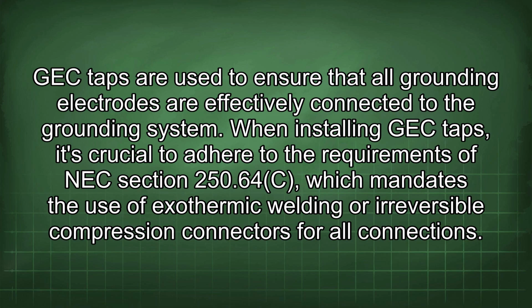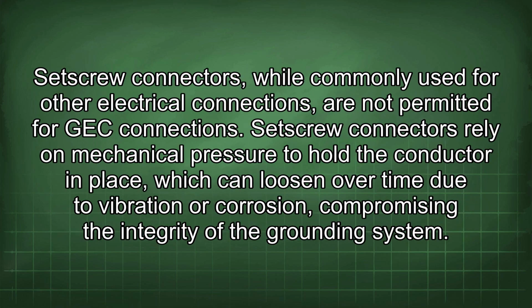When installing GEC taps, it's crucial to adhere to the requirements of NEC Section 250.64(C), which mandates the use of exothermic welding or irreversible compression connectors for all connections. Set screw connectors, while commonly used for other electrical connections, are not permitted for GEC connections. Set screw connectors rely on mechanical pressure to hold the conductor in place, which can loosen over time due to vibration or corrosion, compromising the integrity of the grounding system.